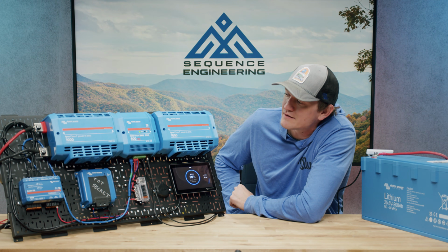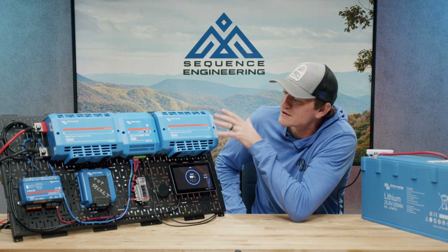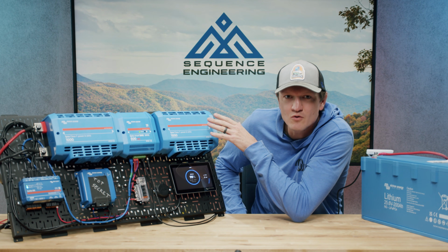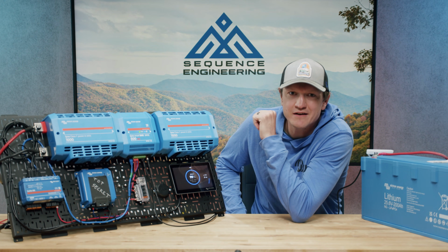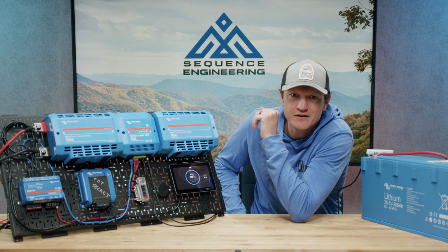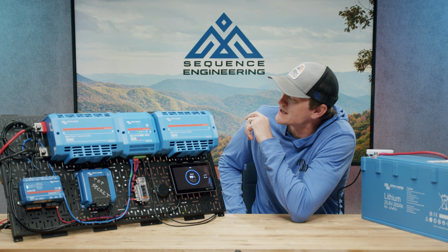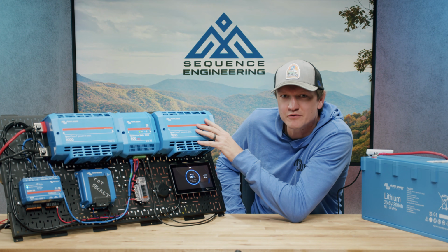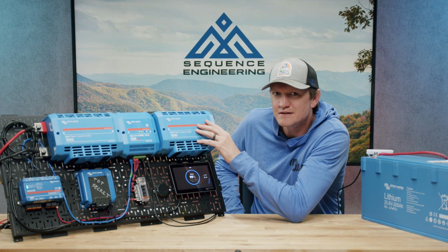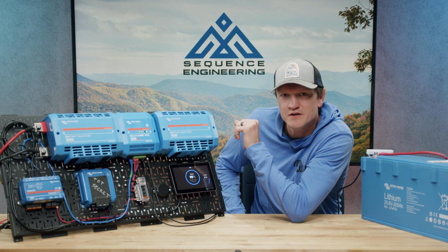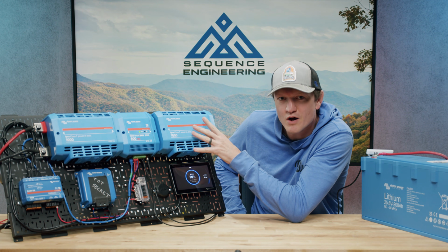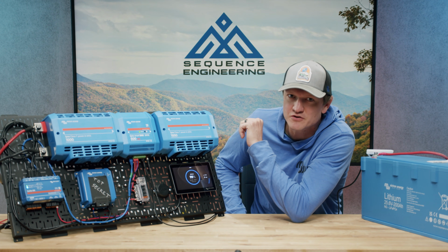At Sequence, we spend a lot of our time working on commercial applications where the client may want to operate at 24 or 48 volts, and they also want to use very large lithium iron phosphate battery banks. In doing that, there's always been a need for a Class T fuse in the system in order to achieve the fusing that we need at those higher voltages and also at that higher AIC rating. Victron has recently launched the Class T Power In, which has now given us the ability to do that in the Victron infrastructure. So I just wanted to spend a few minutes covering this product for you, why it matters, and how you might use it in a system that you're designing.